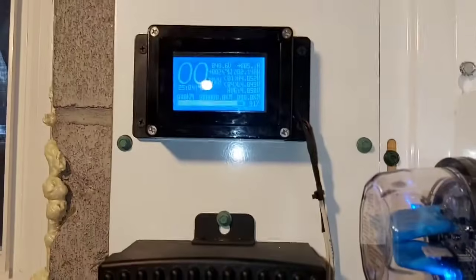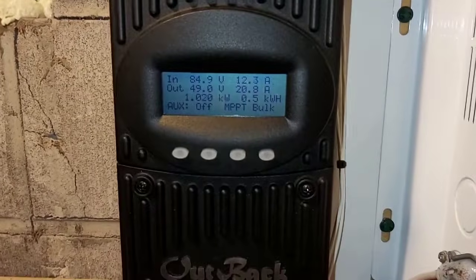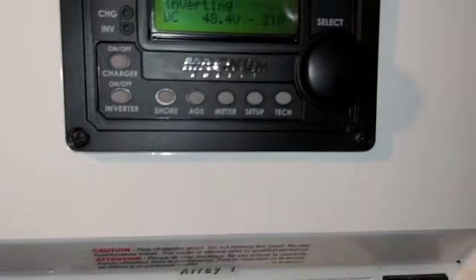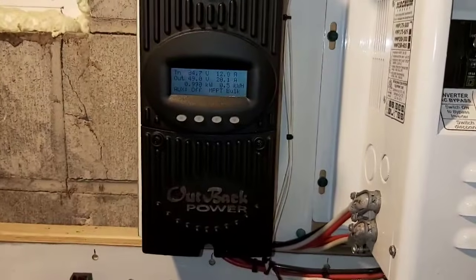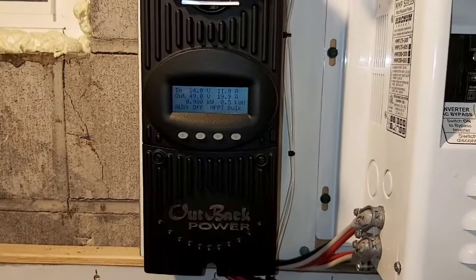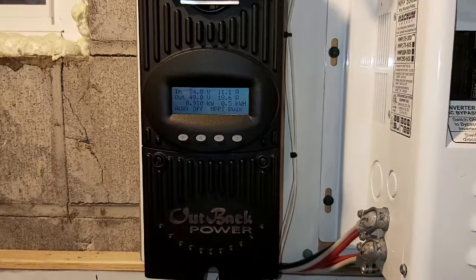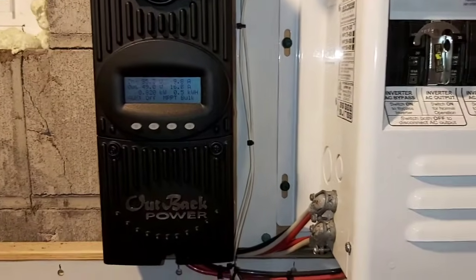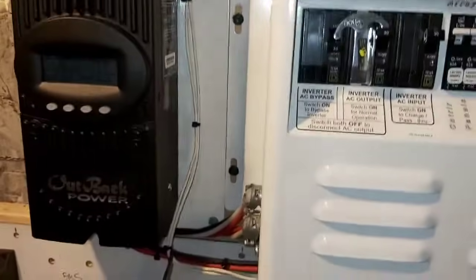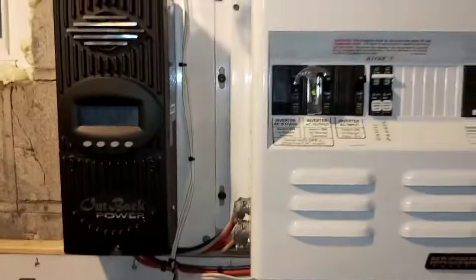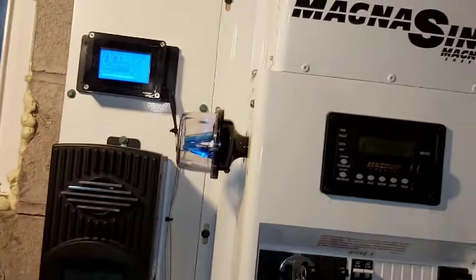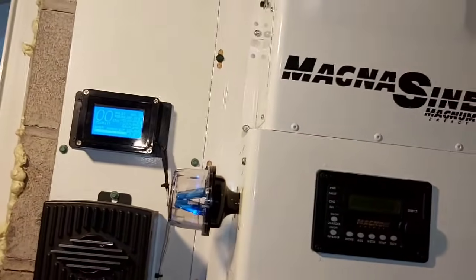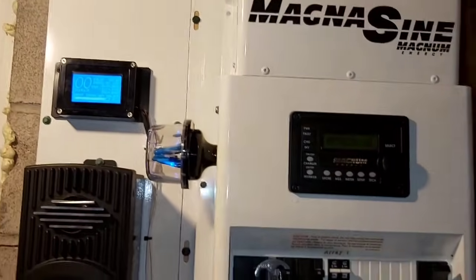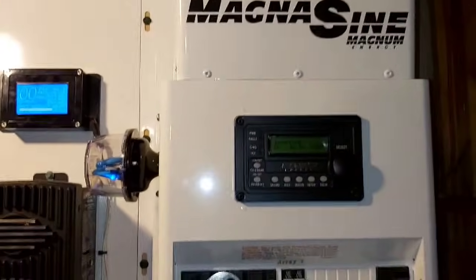Same thing, we're putting 5 amps into the batteries when we're doing 21 amps and 21 amps going out. There's no AC on right now, so it's not making much sense. I'm gonna do some math and see actually what we're taking. There's some losses through the equipment as well, so there will be some discrepancies just from that alone. This is a big transformer, single transformer based inverter, so it could be using up to 100 watts in use.